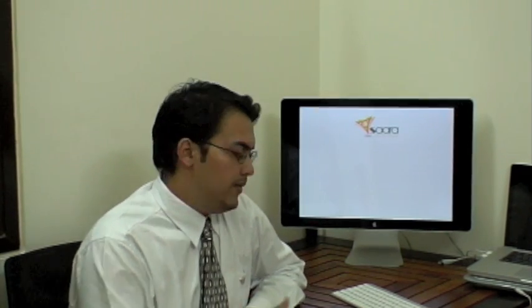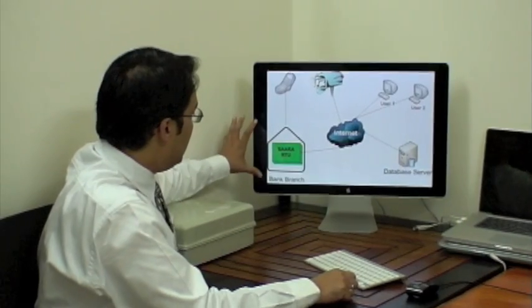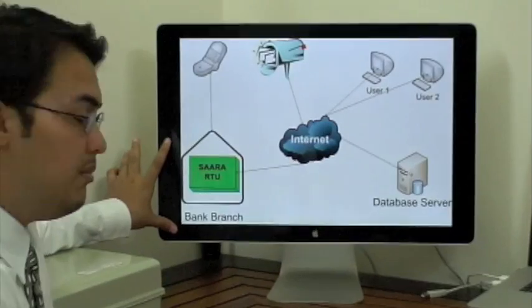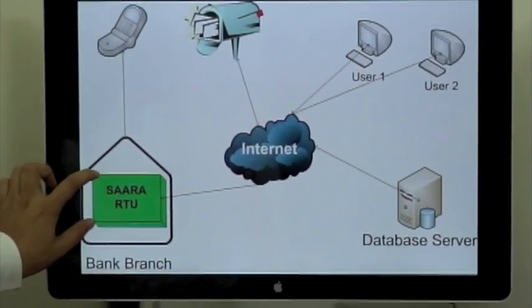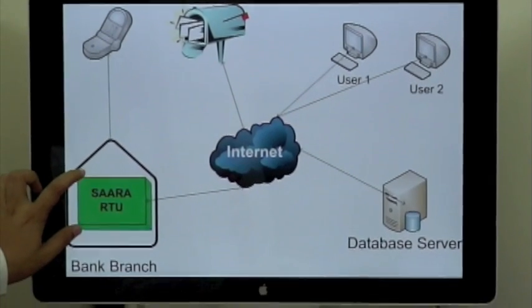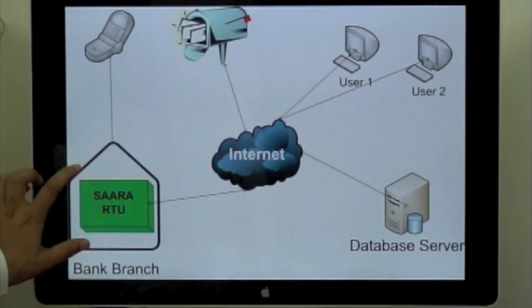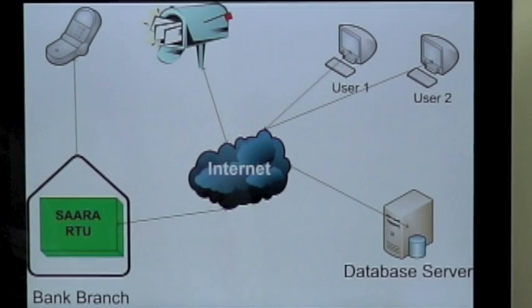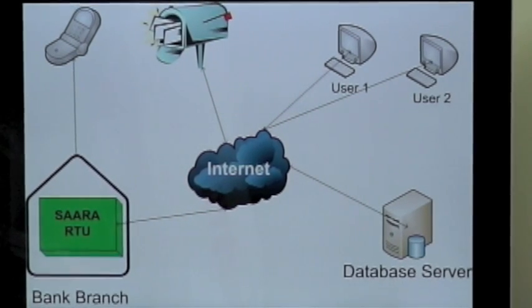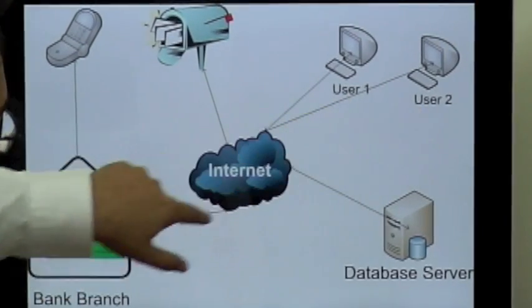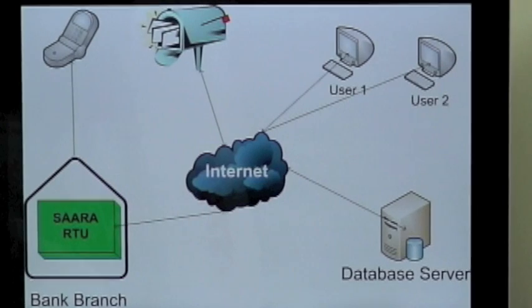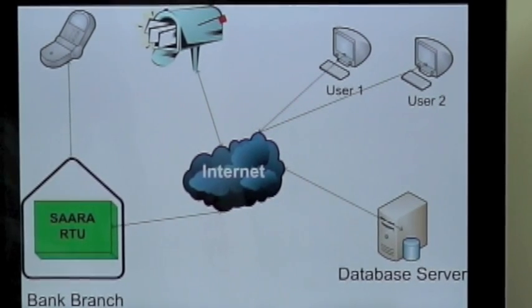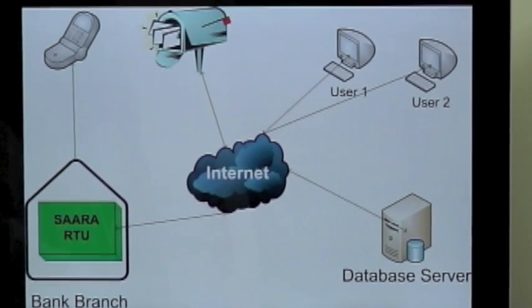Let me give you a brief system overview of the SAARA facility management system. This is where the bank branch is, this is where your facility could be, and we've placed a SAARA RTU which is based on the SBRIO and works on LabVIEW. This pumps information to the internet of the real-time parameters of the energy consumption across the facility, and users can remotely connect to the RTU via our customized front panel and check the real-time parameters as well as historical data.